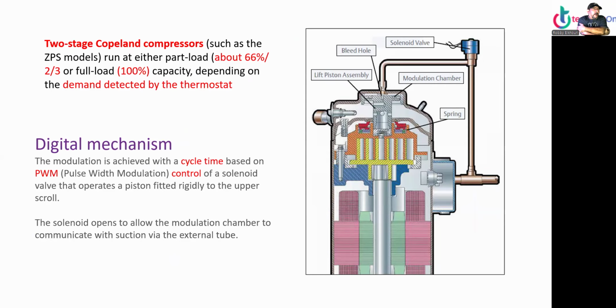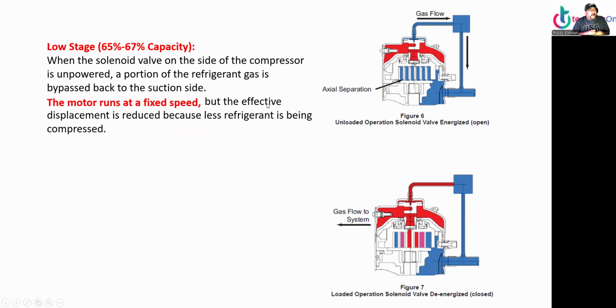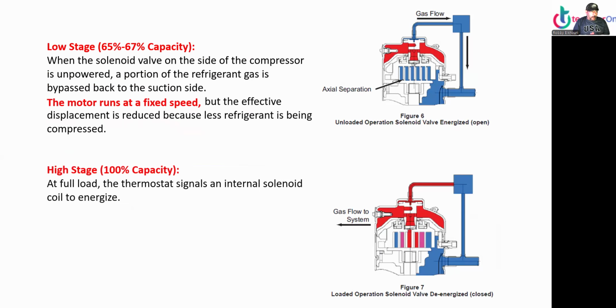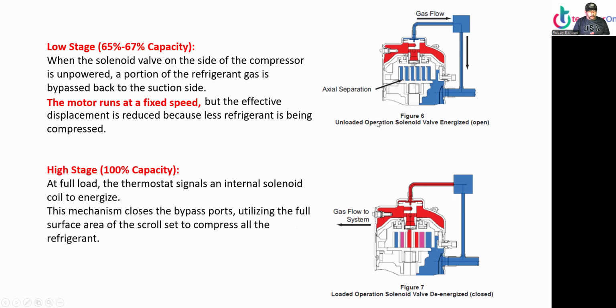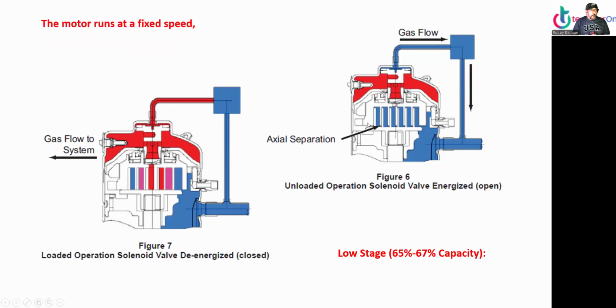The two-stage compressor operates at 60%. The modulation is based on time. The computer tells it when to open and when to close, and it works on time. When the solenoid valve is on, the compressor is unloaded and a portion of the gas is bypassed back to the suction port. The motor is always the same speed, but the effective displacement reduces the volume of the scroll when it turns. So high stage is 100% capacity at full load, with the thermostat signal and internal solenoid energizing. So okay. The motor is always fixed speed, in low stage and high stage.